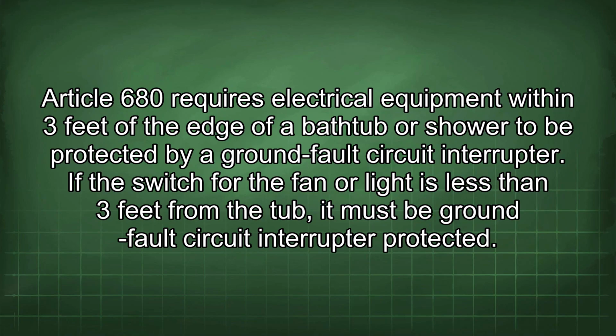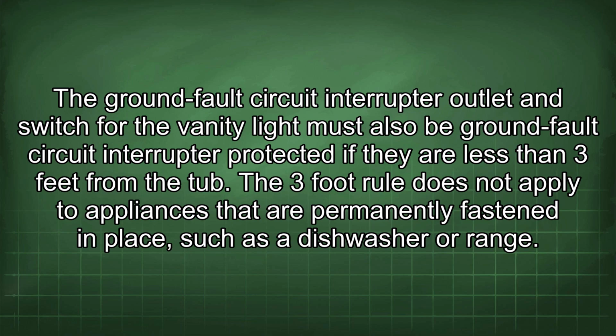Article 680 requires electrical equipment within 3 feet of the edge of a bathtub or shower to be protected by a ground fault circuit interrupter. If the switch for the fan or light is less than 3 feet from the tub, it must be ground fault circuit interrupter protected. The ground fault circuit interrupter outlet and switch for the vanity light must also be ground fault circuit interrupter protected if they are less than 3 feet from the tub.